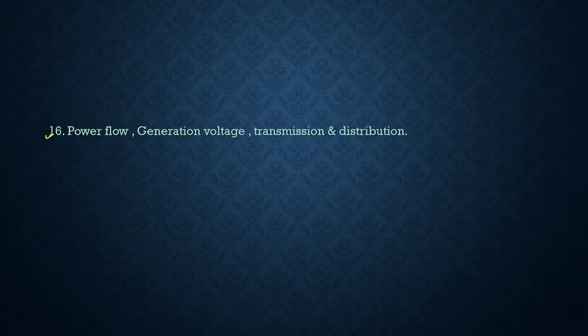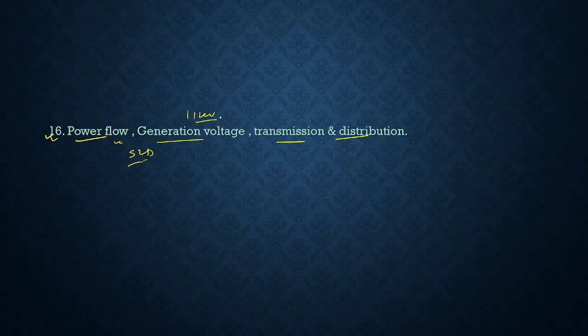And then the power flow and the generation, voltage, transmission, distribution. My previous experience was in a power plant, so they asked, since our plant was connected with four or five plants, how was the power flow of my equipment. You can also show the SLD, single line diagram. My generation voltage was 11 kV. Further it was stepped up to 132 kV, then further stepped up to 400 kV, and the transmission voltage was 400 kV. So these are the basic ideas you can tell the interviewer.